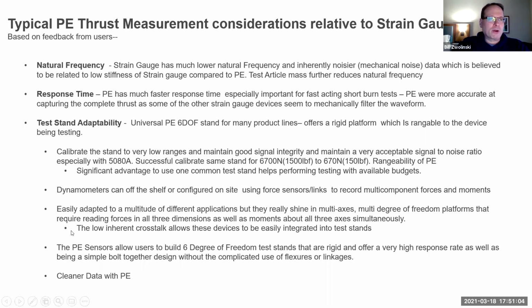I work with folks across the Americas, which is a pretty wide region, and there's quite a bit of use still of strain gauge. I often ask for feedback—why would you want to use piezoelectric versus strain gauge? One of the engineers I work with, probably one of the most power users I know for piezoelectric, also uses strain gauge. He says strain gauge has a much lower natural frequency and is inherently noisier, in his opinion, than piezoelectric.